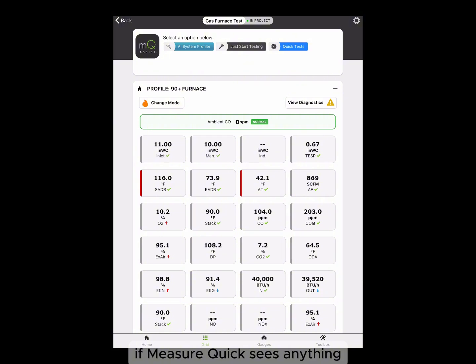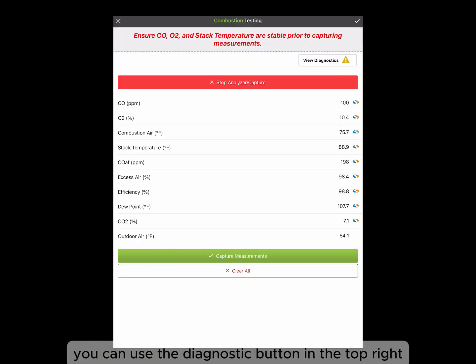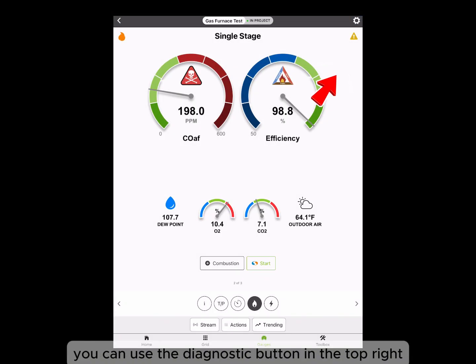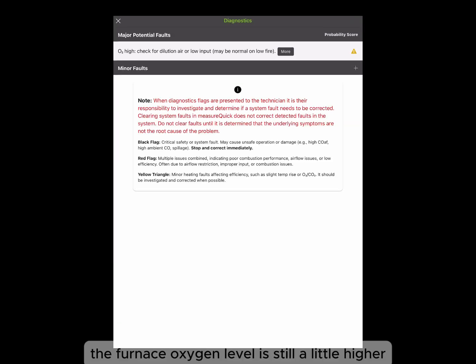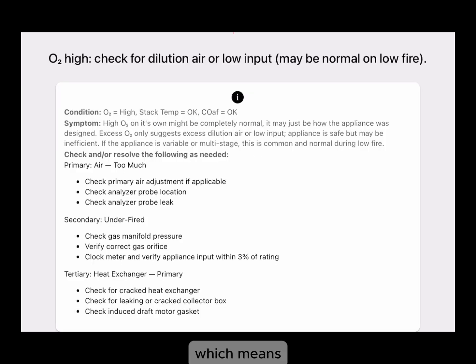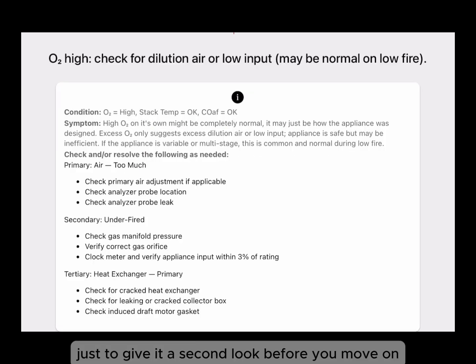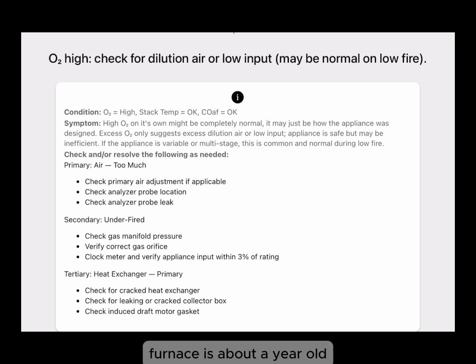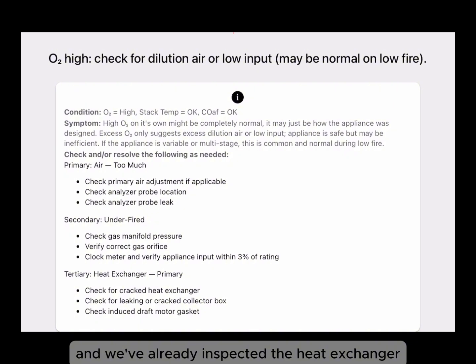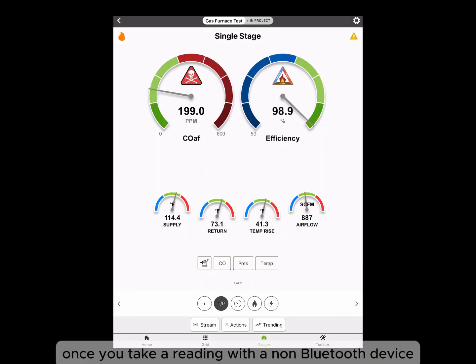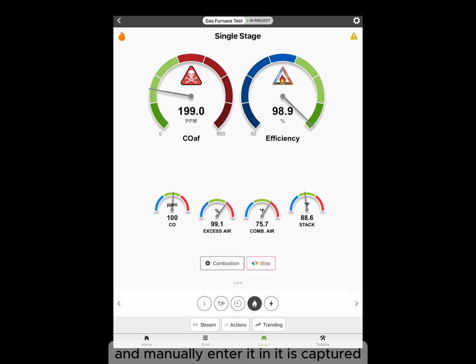If measureQuick sees anything that you need to give further attention to, you can use the diagnostic button in the top right. In this case, the furnace oxygen level is still a little higher than measureQuick would like to see. But it's not a red flag, it's just a yellow caution, which means just to give it a second look before you move on. Sometimes it can just be how the furnace normally operates. The furnace is about a year old and we've already inspected the heat exchanger, so we know there's no issues there. Once you take a reading with a non-Bluetooth device and manually enter it in, it is captured.